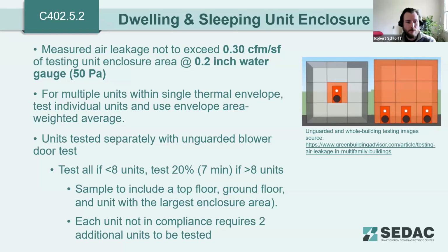If you have a building with multiple units, units should be tested separately with unguarded blower door tests. If there are fewer than 8 units, you test all of the units. If there are more than 8 units, you test at least 20% of them, which is a minimum of 7. This sampling of units must include a top floor unit, a ground floor unit, and a unit with the largest enclosure area, so whatever the largest unit happens to be within the building. And then each unit not in compliance requires 2 additional units to be tested. So that just means you want to pay attention as much as you can to ensure the testing doesn't take longer than it needs to. Pay attention to air sealing details within the units to make sure that you don't have to keep testing further units.